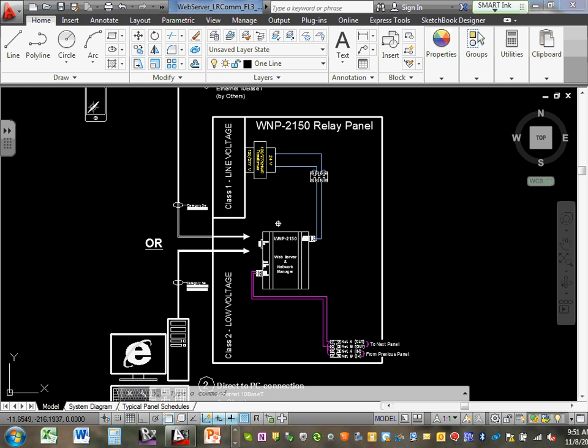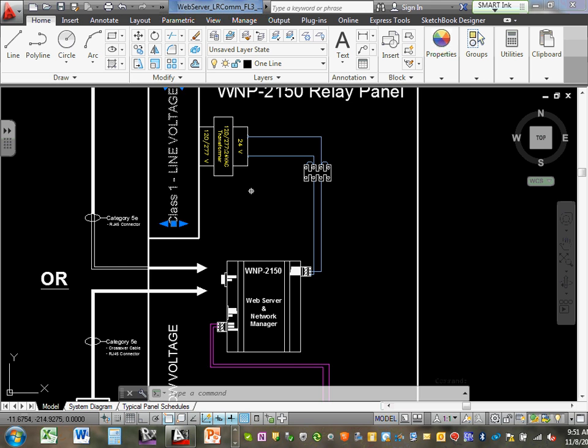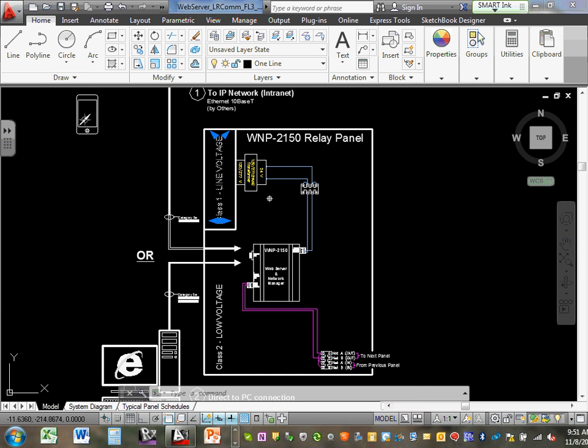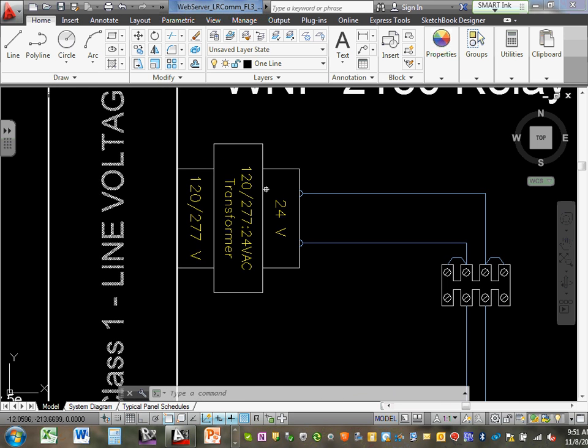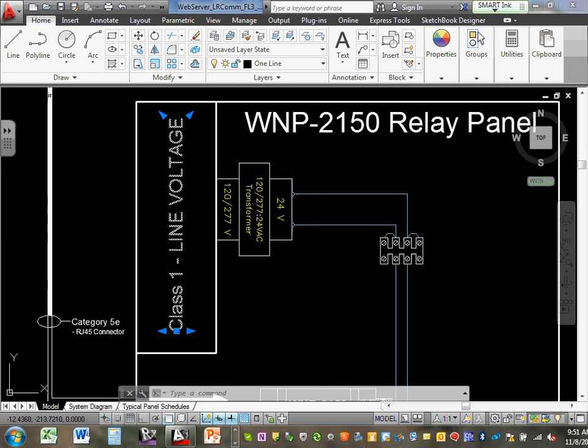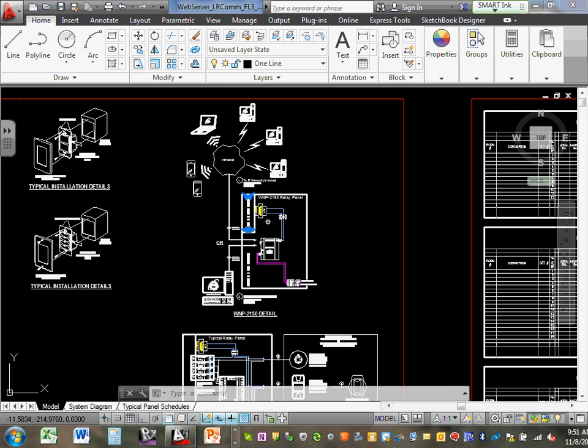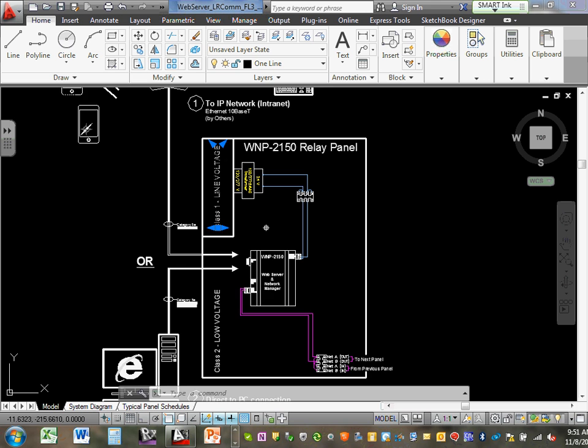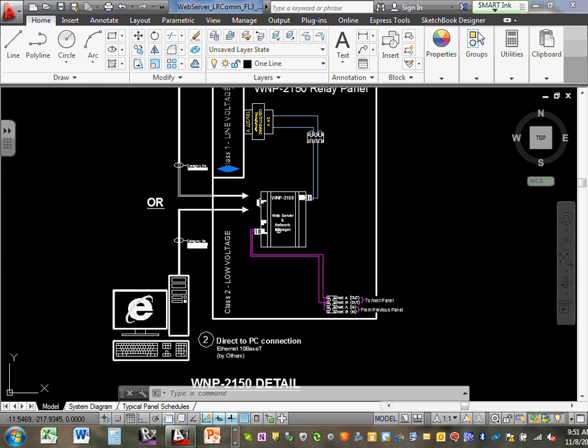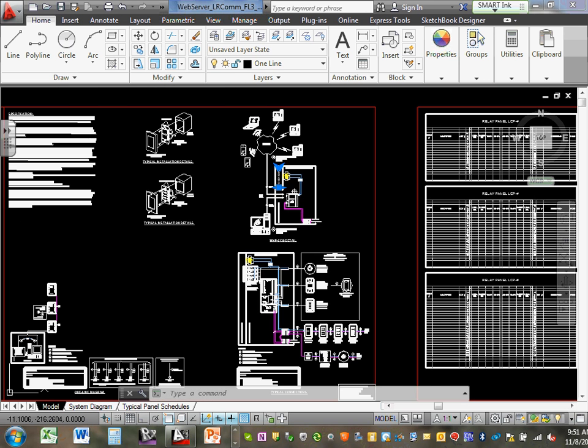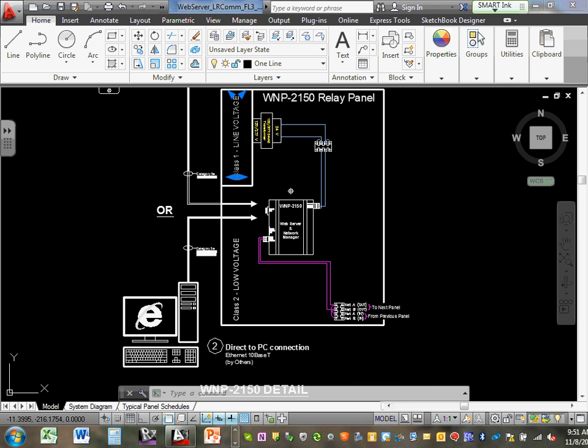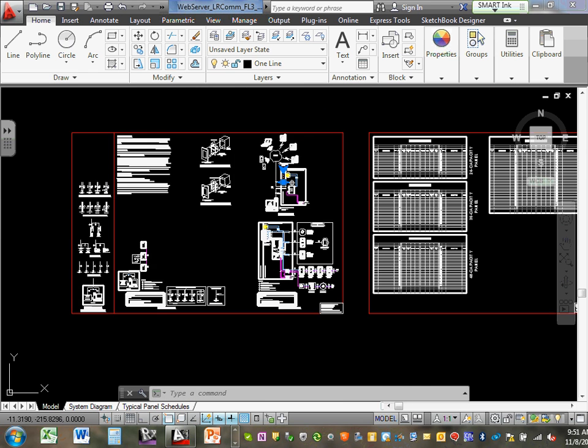Okay, so all we're showing you here is that we've got a class 1 line voltage section of the panel. That's where the relay or the transformer is going to fit. So I've got a transformer that has to live in there. It takes a 120 or 277 volt feed, and that's what powers my panel. So there's my transformer on the line voltage side. That feeds the DIN rail and feeds all the relays on the low voltage side. So I have to have that primary feed just to energize all the control electronics. And that has to happen in each and every panel.